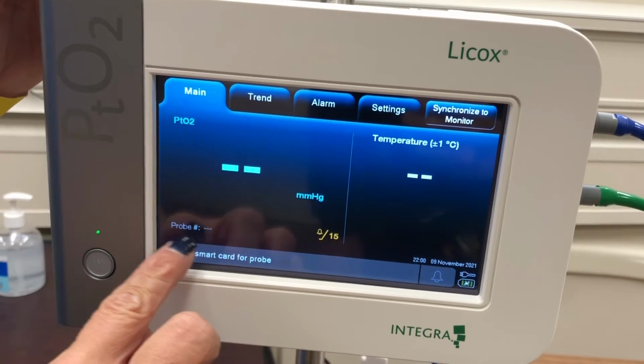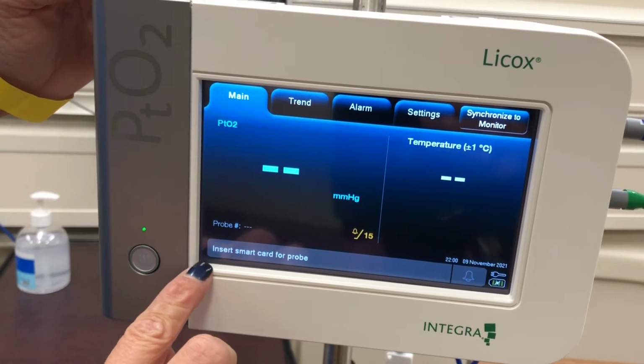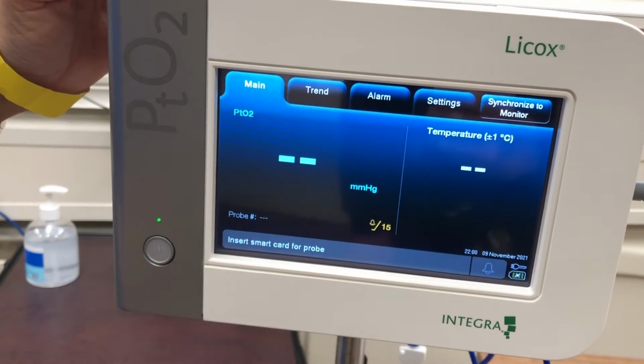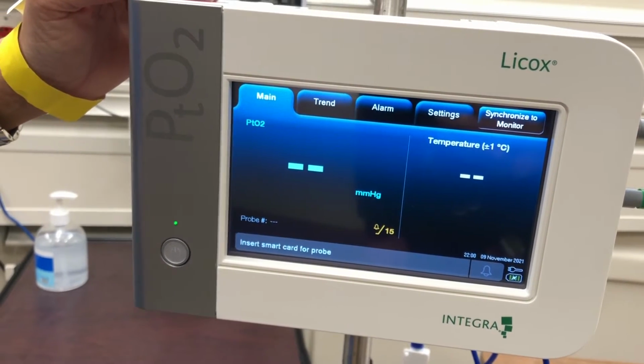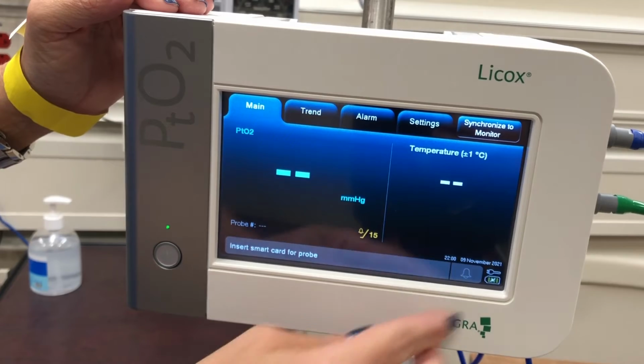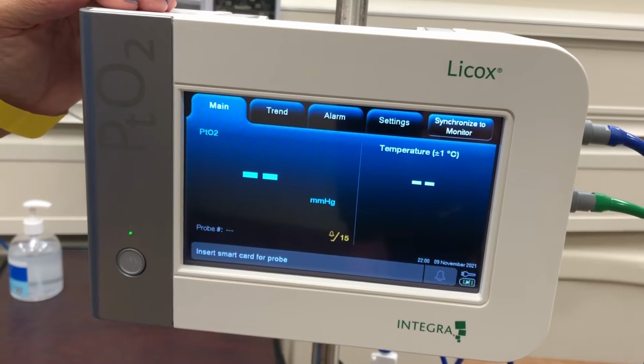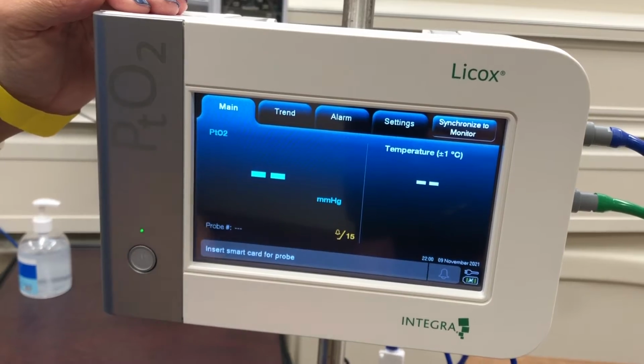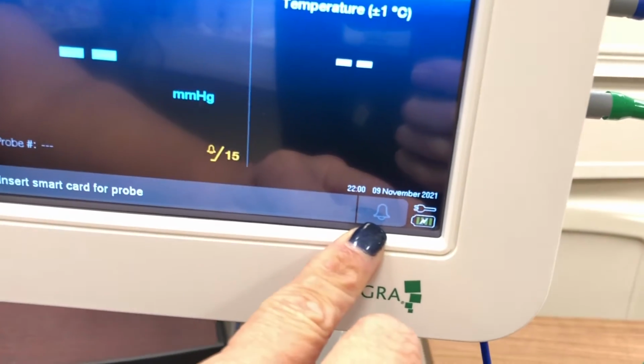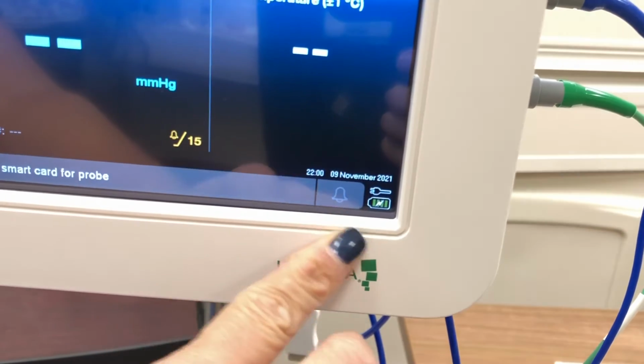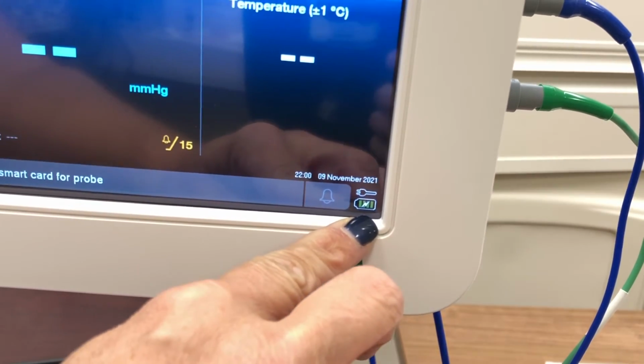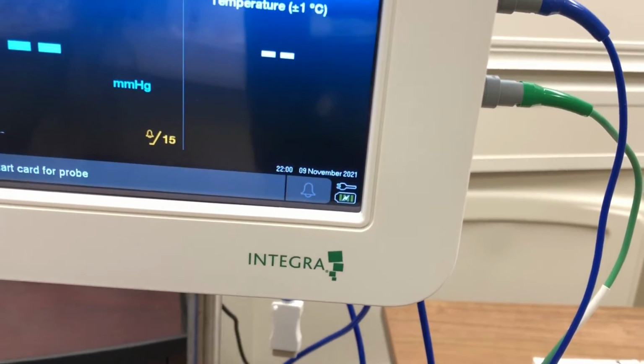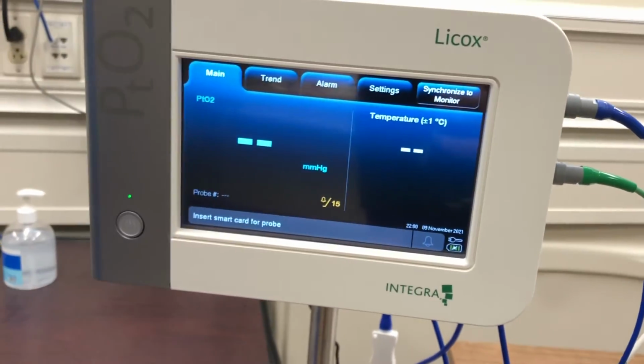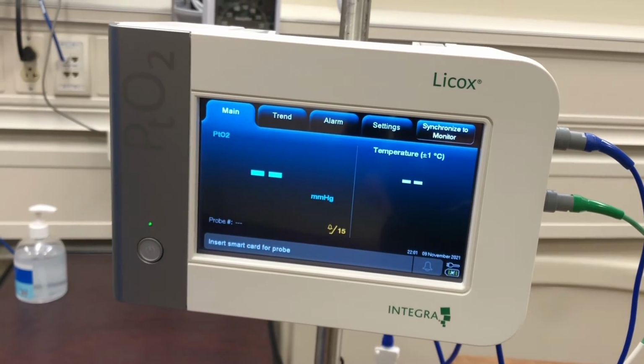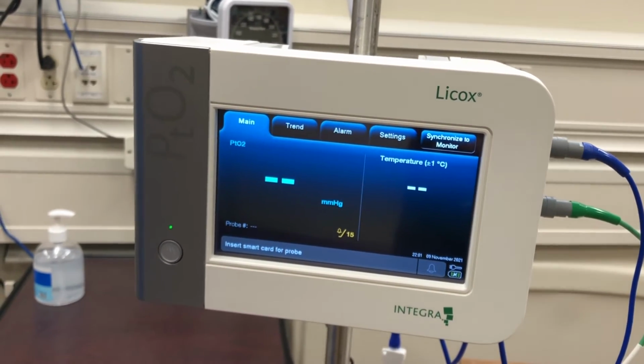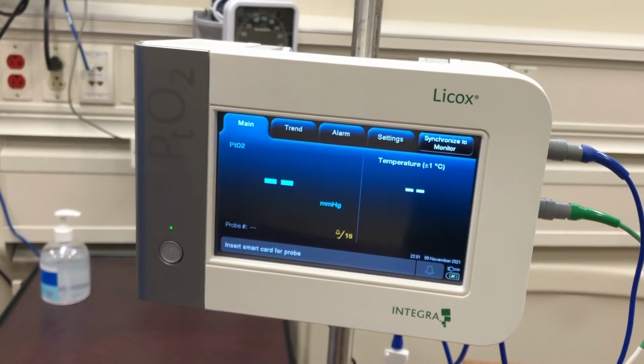You know that there's no probe connected because there are dashes down here. It literally tells you to insert the smart card for the probe, which we're going to do prior to any placement of a probe into the brain. On the right-hand side of the screen, you're going to see the temperature, and that is the portion that's calibrating during that warm-up. Down here, you see the alarm bell. That's what will siren. All of us nurses really love alarms, but here is a battery indicator as well, and it lets you know that there is a plug that's actually being plugged into the wall. Of note, this takes about 5 hours to fully charge once the battery has discharged, and you only have a power reserve on the battery of 1.5 hours.